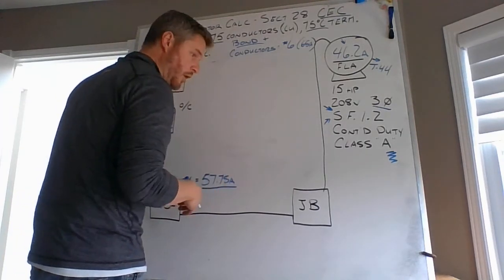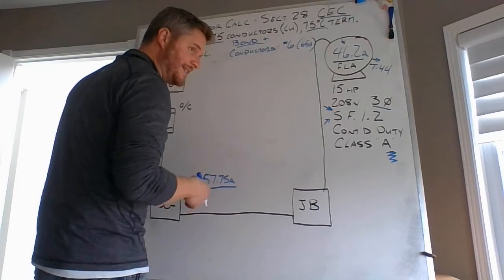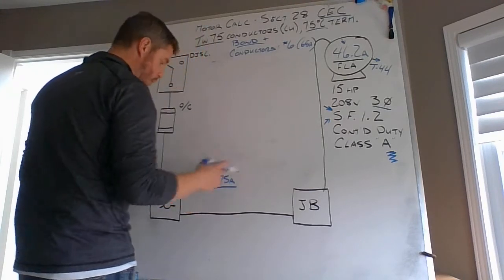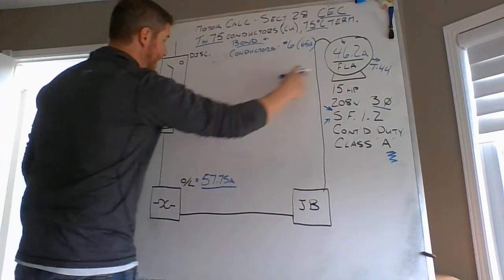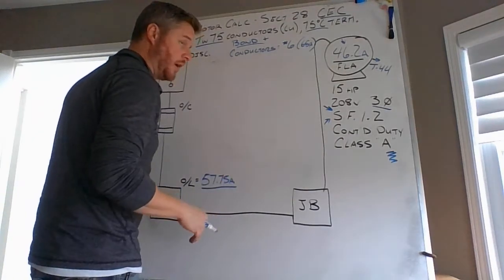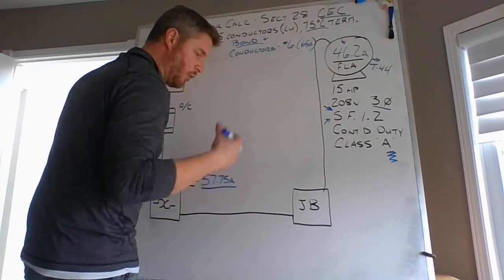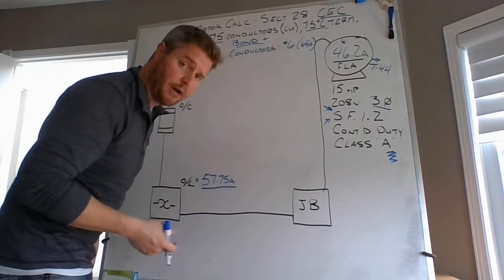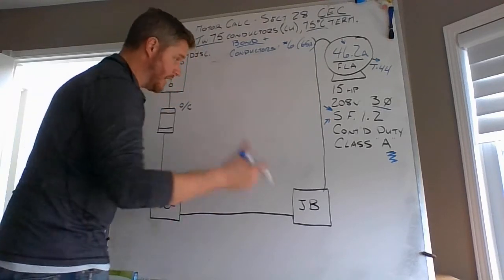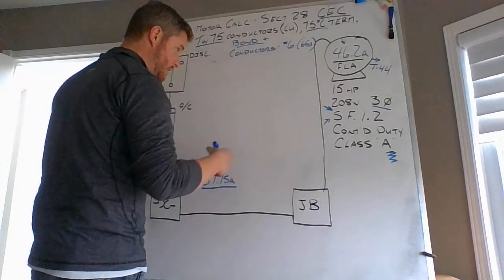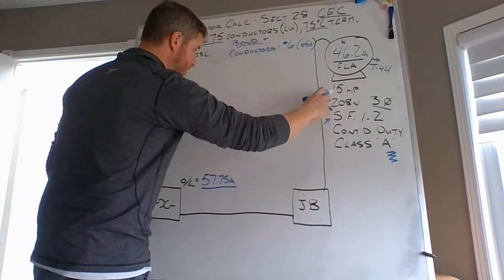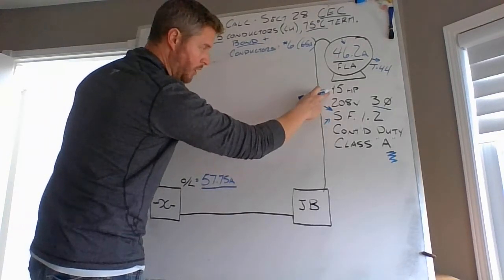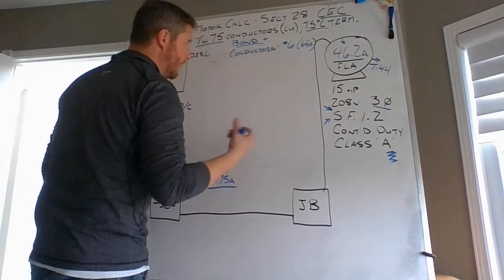Bottom left-hand corner on your overload relay for your IEC starter. You wire in those overloads to protect that motor that you fire every single week, whether it's with a flow switch or a start-stop station or a parallel start-stop station. It's the same motor every single time, 3-phase. And it is 208 volts. However, it's not 15 horsepower. It's a lot less than that.